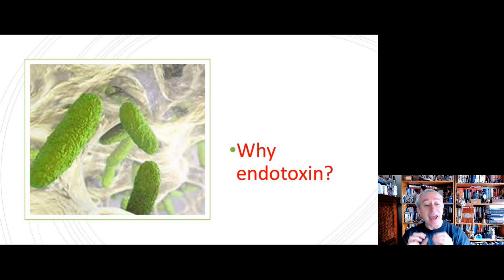So why is there a focus on endotoxin, and why is endotoxin used as the control for the depyrogenation tunnel? Well, endotoxin is a fragment of the cell wall of a very common morphological group of bacteria - gram-negative bacteria - and it's generally the substance that's most resistant to heat. If we're going to challenge a depyrogenation tunnel, we want to make sure that we're using something that is the most resistant to heat. An ordinary autoclave would not be sufficiently hot to kill endotoxin. Autoclave destroys all bacterial cells and spores, but the fragments of the cell wall that can cause the pyrogenic reaction can survive. We've got to get them to hotter temperatures, create super heat. So that's my first point.